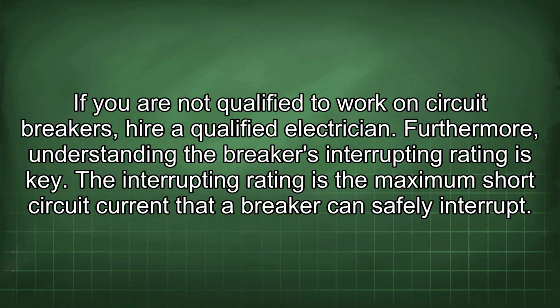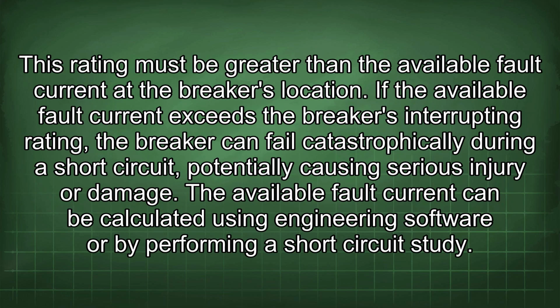Furthermore, understanding the breaker's interrupting rating is key. Interrupting rating is the maximum short circuit current that a breaker can safely interrupt. This rating must be greater than the available fault current at the breaker's location. If the available fault current exceeds the breaker's interrupting rating, the breaker can fail catastrophically during a short circuit, potentially causing serious injury or damage.